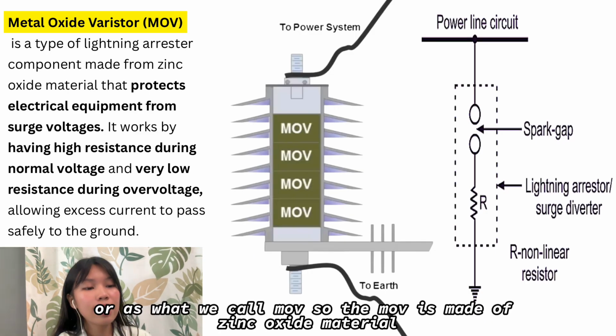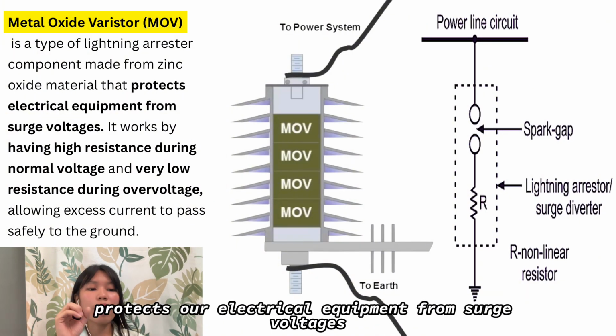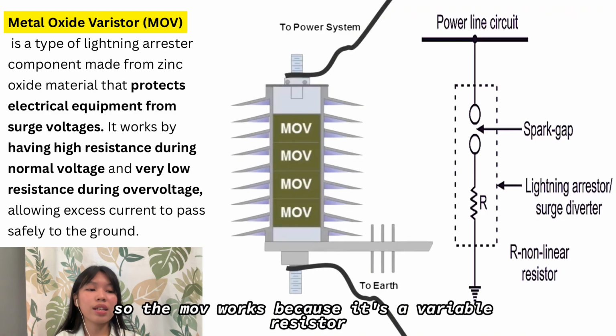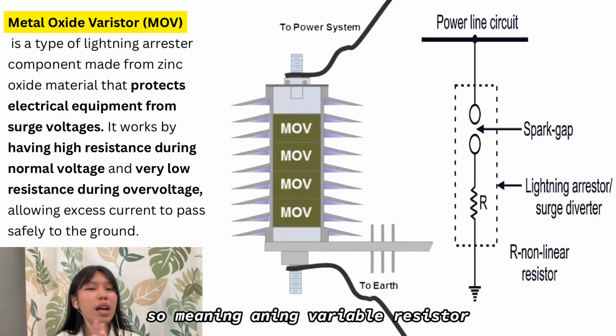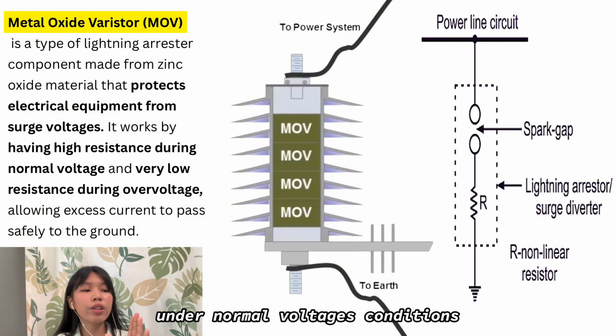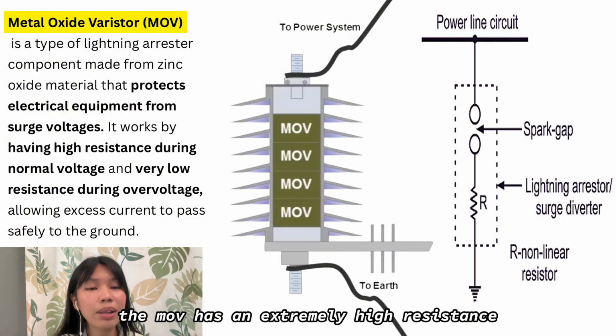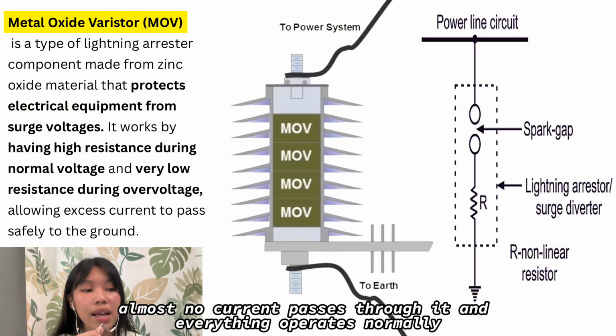Now let's talk about the heart of the lightning arrestor, the metal oxide varistor, or MOV. The MOV is made of zinc oxide material. It is the key component that directly protects our electrical equipment from surge voltages. The MOV works as a variable resistor. Under normal voltage conditions, the MOV has an extremely high resistance. Almost no current passes through it, and everything operates normally.